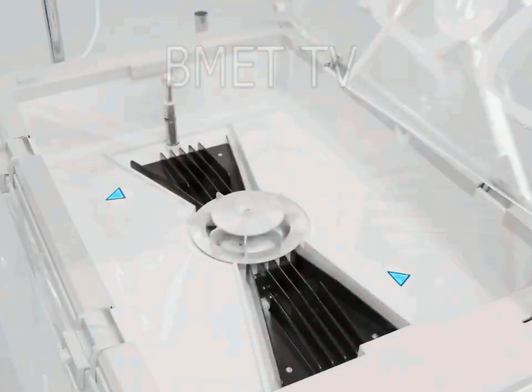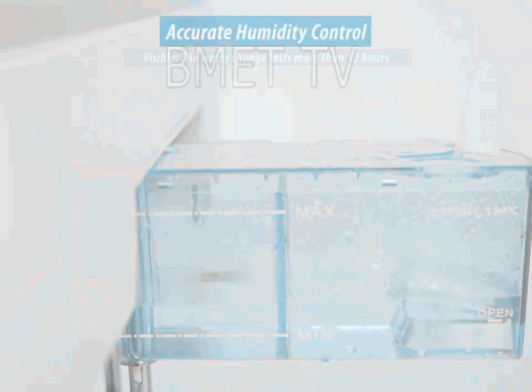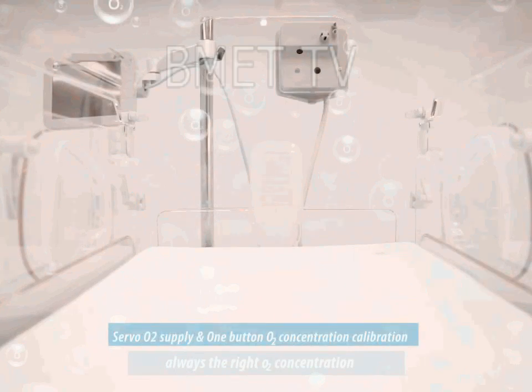A fan blows filtered ambient air over a heating element and a water container. Through a control valve, additional oxygen can be supplied to the air. The moistened, heated, and enriched air now flows into the above cabinet with the baby. One part of the air escapes from the cabinet through vent holes, another part gets back into the air processing. The major components of a baby incubator are the fan, filters, heater, temperature control, humidity control, and oxygen control.